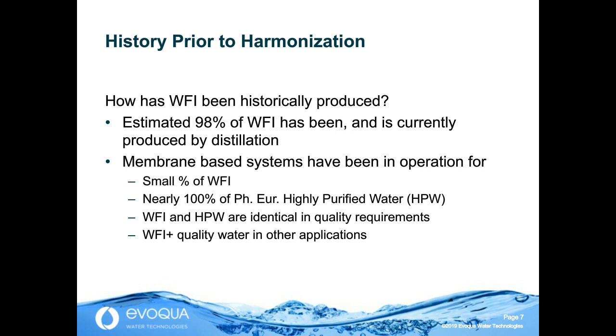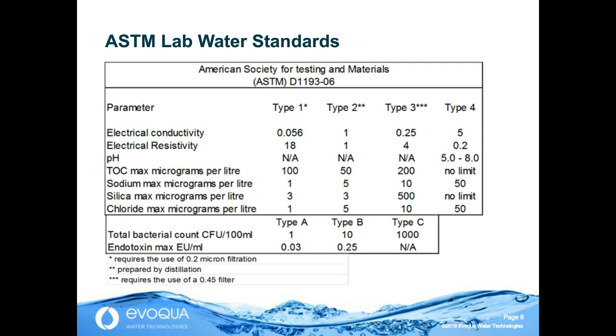If we look at laboratory water, ASTM has several standards for lab water that are popular. If we look in the type 1 column, we will see that the conductivity is nearly the theoretical limit and much lower than USP conductivity. The total organic carbon is 100 parts per billion versus 500 parts per billion for WFI. And if you look below that at type A water, the micro limit for ASTM type 1, type A is 1 log tighter than WFI, and the endotoxin is nearly a log tighter.